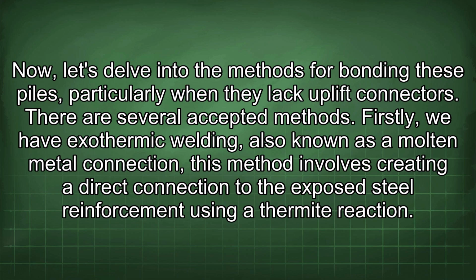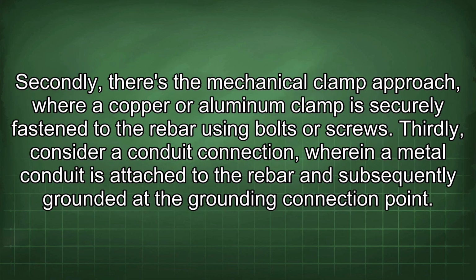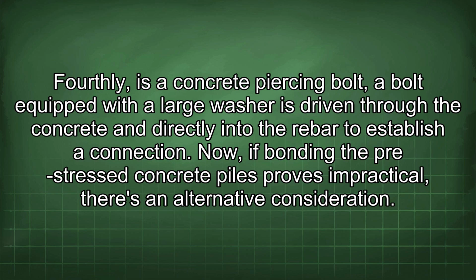There are several accepted methods. Firstly, we have exothermic welding, also known as a molten metal connection. This method involves creating a direct connection to the exposed steel reinforcement using a thermite reaction. Secondly, there's the mechanical clamp approach, where a copper or aluminum clamp is securely fastened to the rebar using bolts or screws. Thirdly, consider a conduit connection, wherein a metal conduit is attached to the rebar and subsequently grounded at the grounding connection point. Fourthly, is a concrete piercing bolt. A bolt equipped with a large washer is driven through the concrete and directly into the rebar to establish a connection.